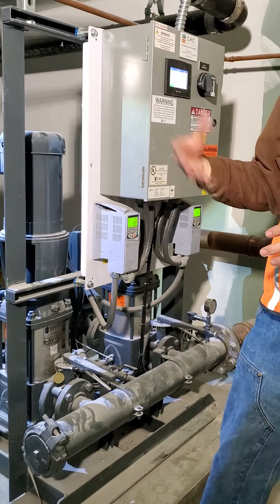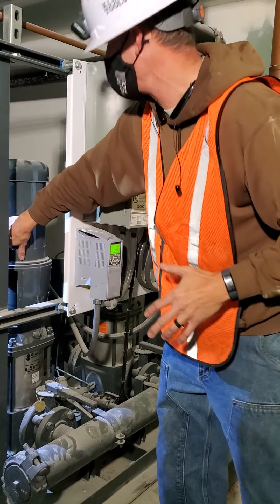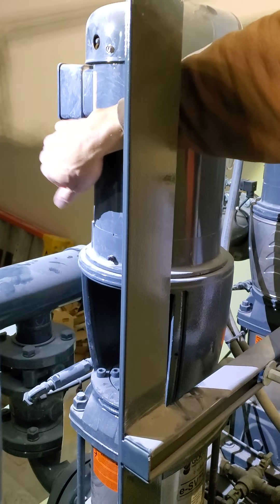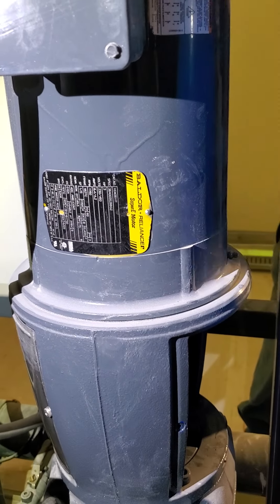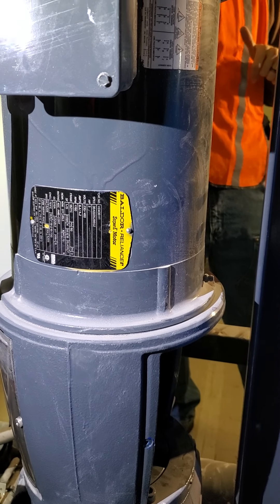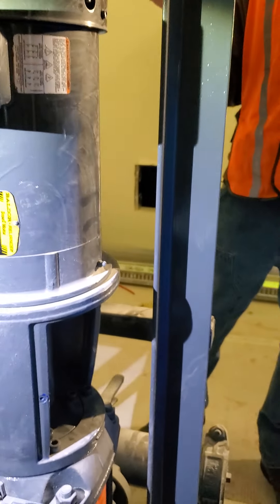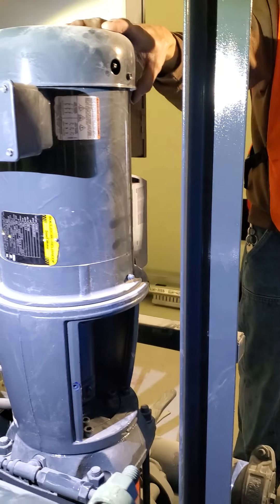On these pumps, the only maintenance is greasing the bearings. It has a grease fitting right here and another one right here. People always ask how often you're supposed to grease them — to get that answer, you'd want to look up the model number on the Baldor website. It'll tell you based on run hours how often to grease it and how much grease to add. That's the only maintenance on these pumps — just grease the bearings according to run time.